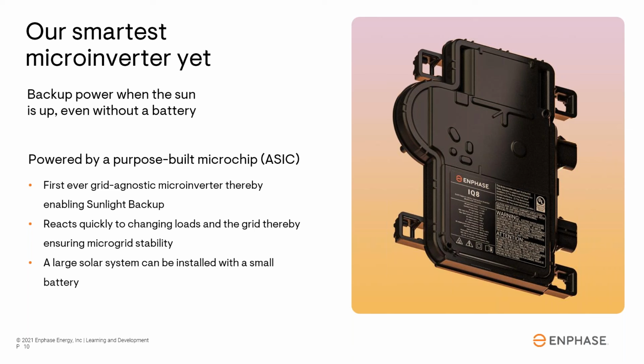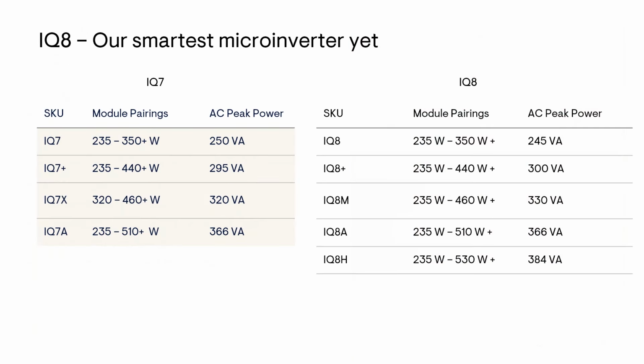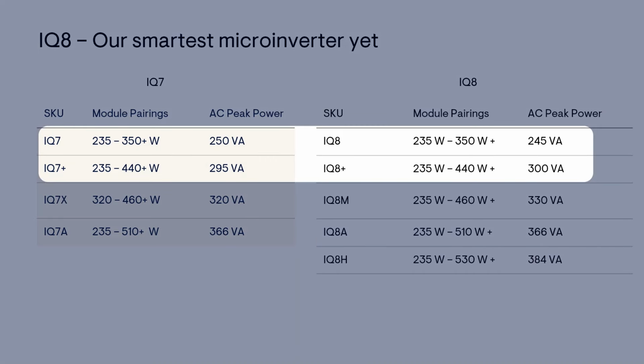Naturally, you also have all the same benefits of distributed architecture, such as higher energy yield, minimized impact of shade, and no single point of failure. The IQ8 is available in 5 models covering a wide range of power. The IQ8 and 8 Plus have similar power ratings to their IQ7 counterparts, as you can see. This makes it easy for designers to change plans from the 7 to the 8 if desired. For example, the same number of IQ8s can be installed per branch circuit as an IQ7.